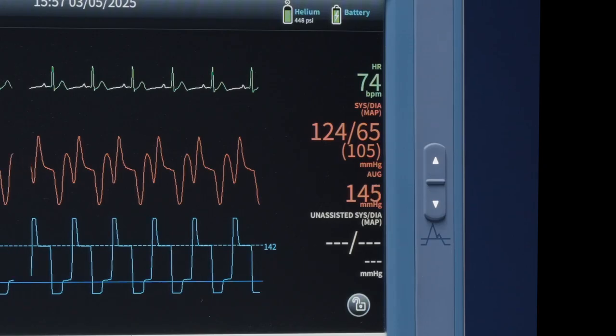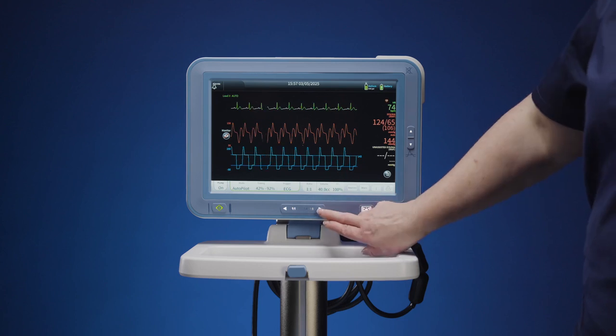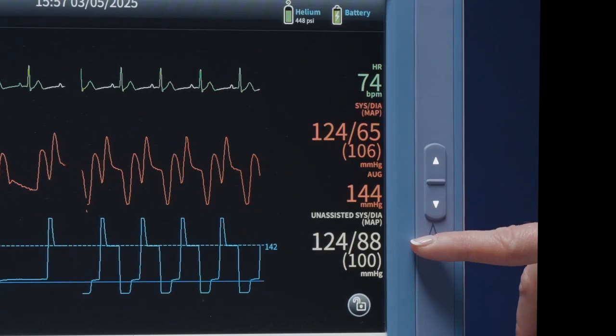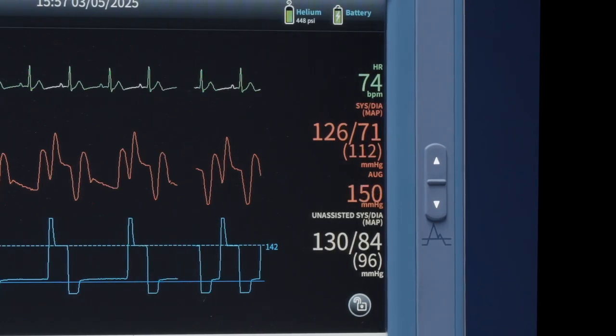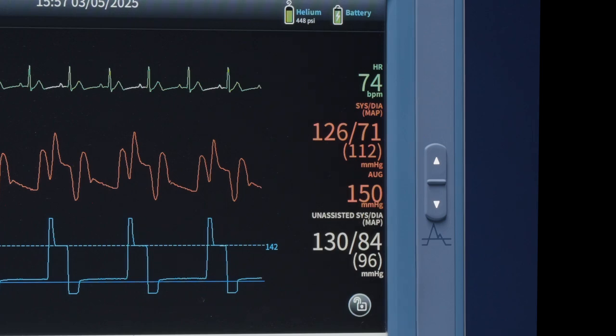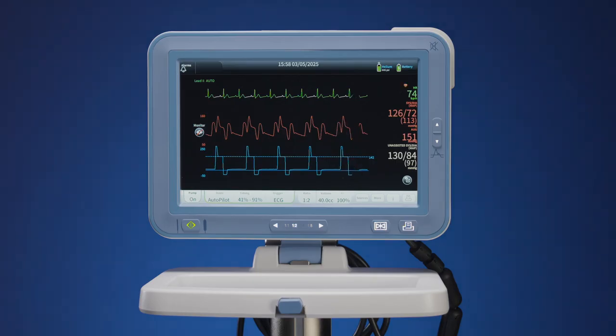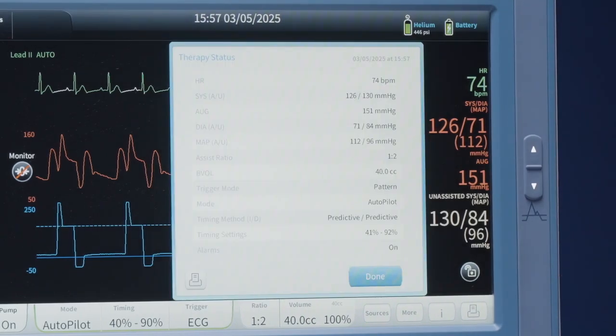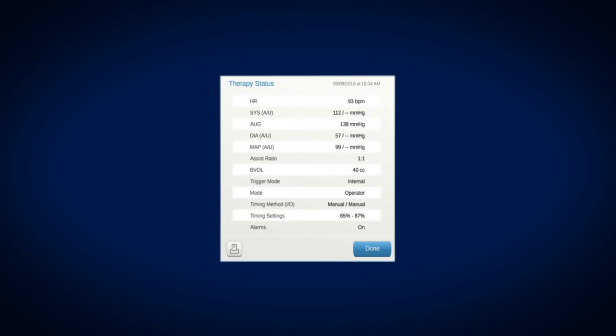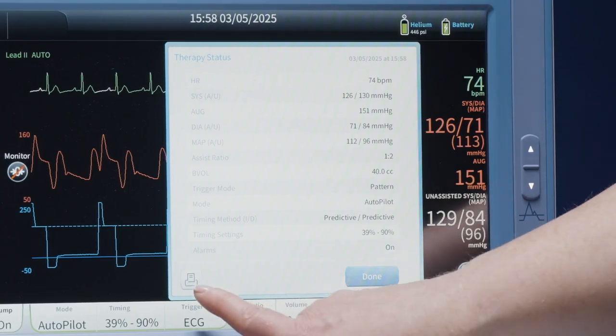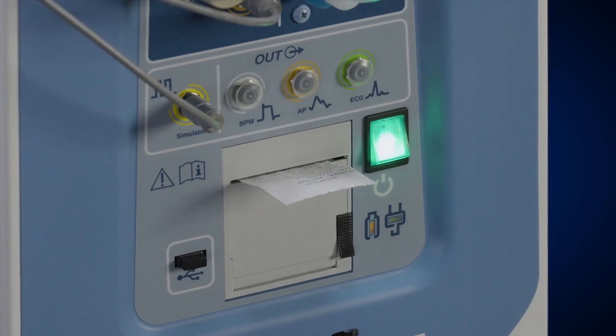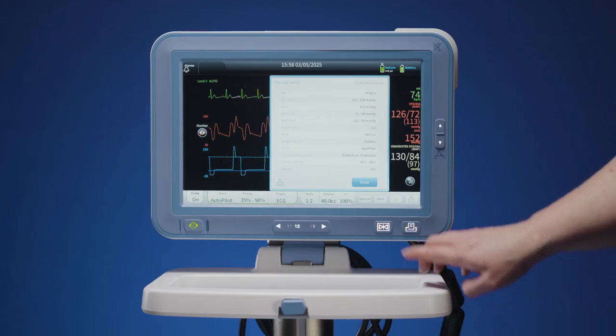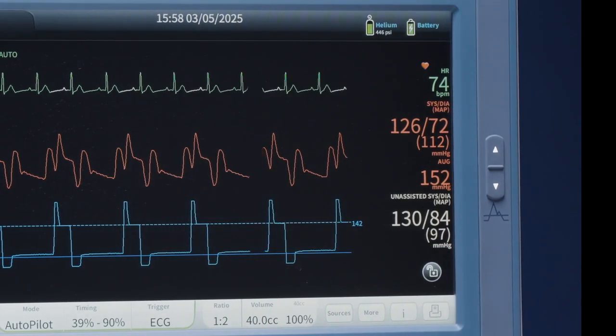The red pressure readings are the assisted beats. When the assist ratio is 1 to 2 or lower, the values displayed in white are for the unassisted beats. A therapy report summarizes the IABP therapy control setting and the patient hemodynamics. By touching the display in the hemodynamic area of the screen, the therapy status report displays. To print this page, press the printer icon button in the lower left corner of the menu display. To close the menu, press the Done key.